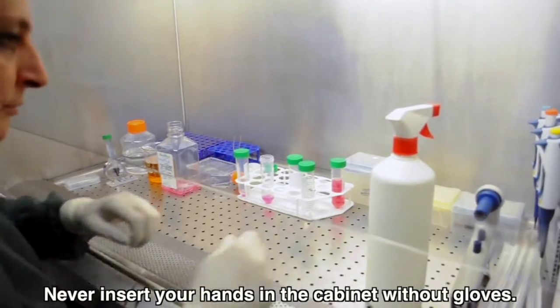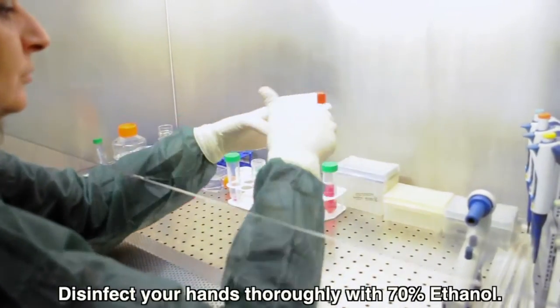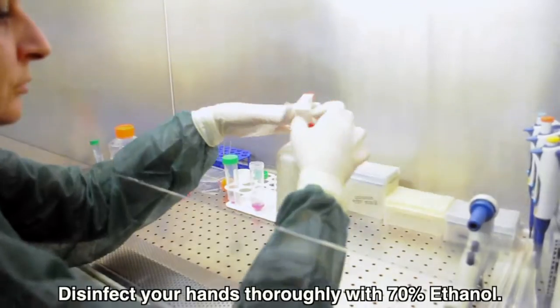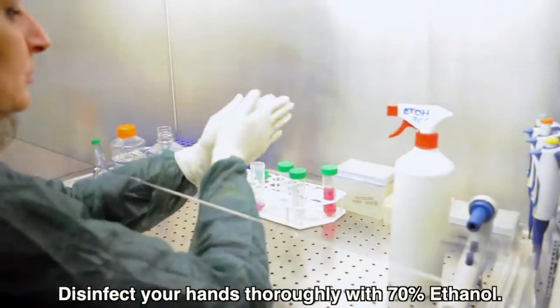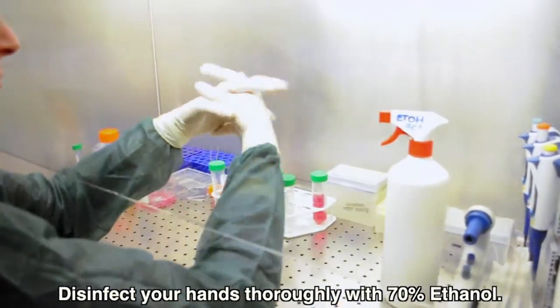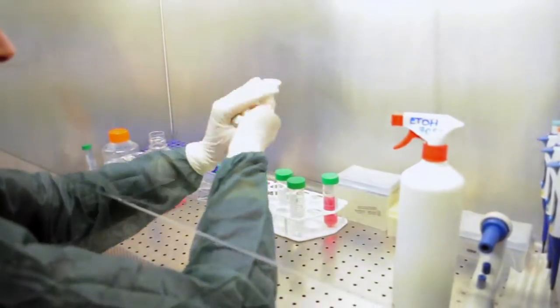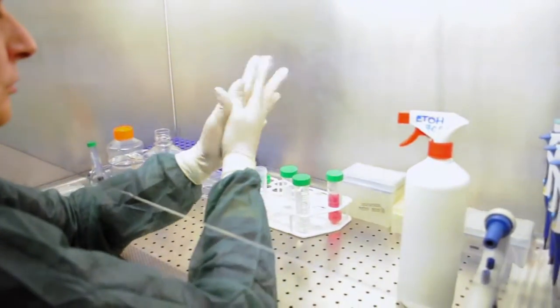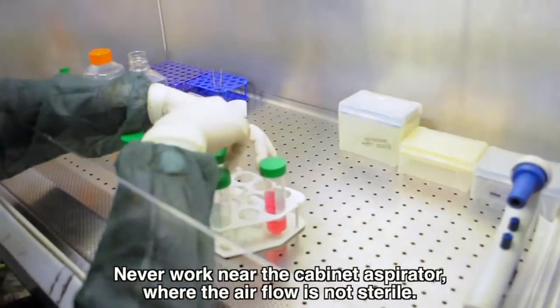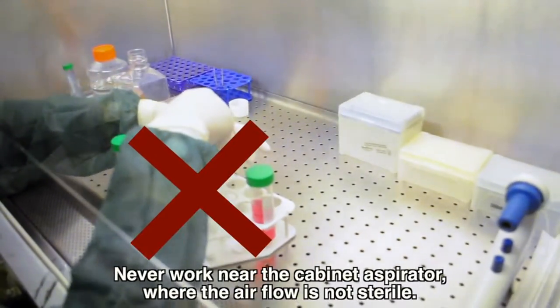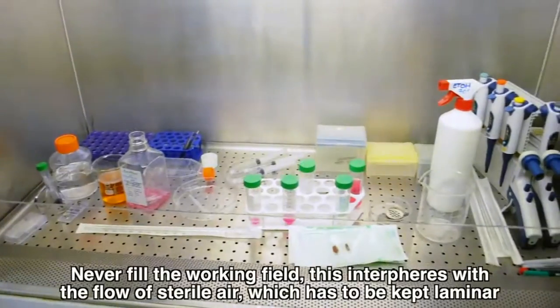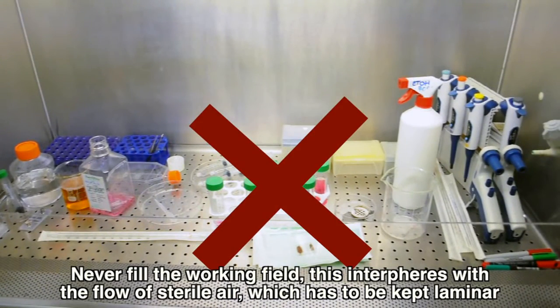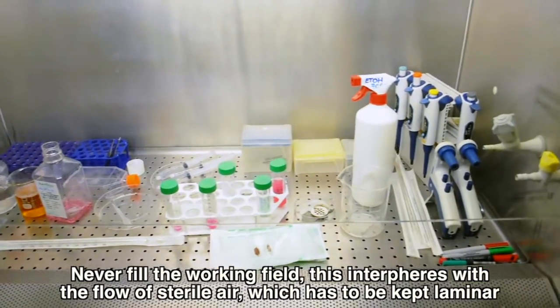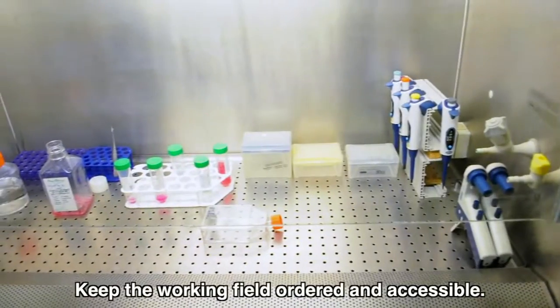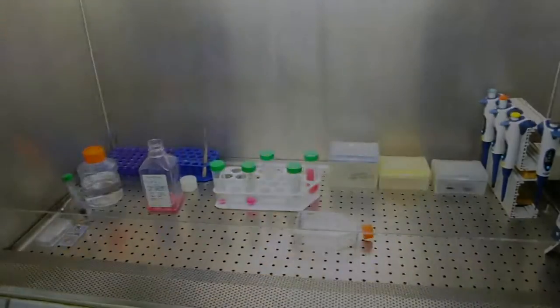Never insert your hands in cabinet without gloves. Disinfect your hands thoroughly with 70% ethanol. Never work near the cabinet aspirator where the airflow is not sterile. Never fill the working field. This interferes with the flow of sterile air, which has to be kept laminar. Keep the working field ordered and accessible. Always refer to the user manual.